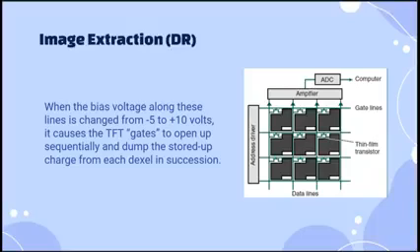Okay, for each particular TFT, the change in voltage causes a channel of conductivity to be opened up along the semiconductor material. Okay, so since we changed the voltage from -5 to +10, a channel of conductivity will be opened along the semiconductor material, which is this area here, the fill factor or the Dexel detector area. Okay, the charge flows down a data line to an amplifier which boosts the signal before sending it through an ADC into the computer.